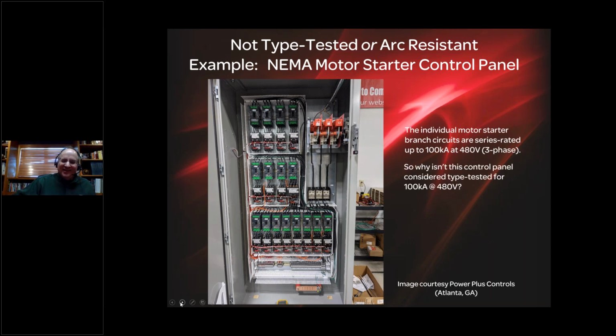So the question is, why isn't this control panel considered type tested? And the answer is, it's not about just the component rating inside. It's about the enclosure. If an arc flash event was initiated at either of the points I'm showing here, there is no guarantee that this enclosure door would remain closed. The only way I could verify that it'll remain closed and not break open is to take it to a high power test lab and test it for whatever amount of fault current I want to rate it to and verify it maintains enclosure integrity.